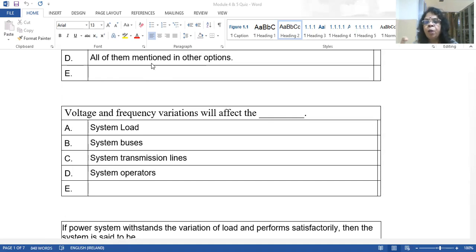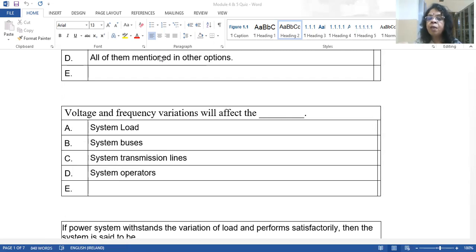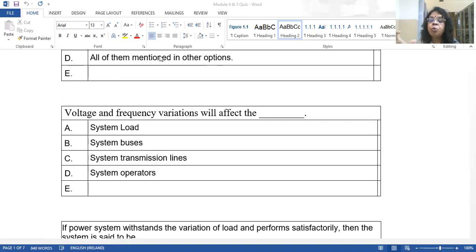Whenever we have a load, we characterize it by active power and reactive power drawn. We normally have four parameters defined for different types of loads: ∂P/∂V — how active power depends on voltage; ∂P/∂F — how active power changes with frequency; and similarly ∂Q/∂V and ∂Q/∂F. These parameters are specific to the type of load. Generally, active power drawn by the load is more dependent on voltage magnitude, but this depends on load type — AC machines, air conditioners, washing machines, industrial loads, pumps, motors, lighting (fluorescent, incandescent), arc furnaces — each has different characteristic parameters.